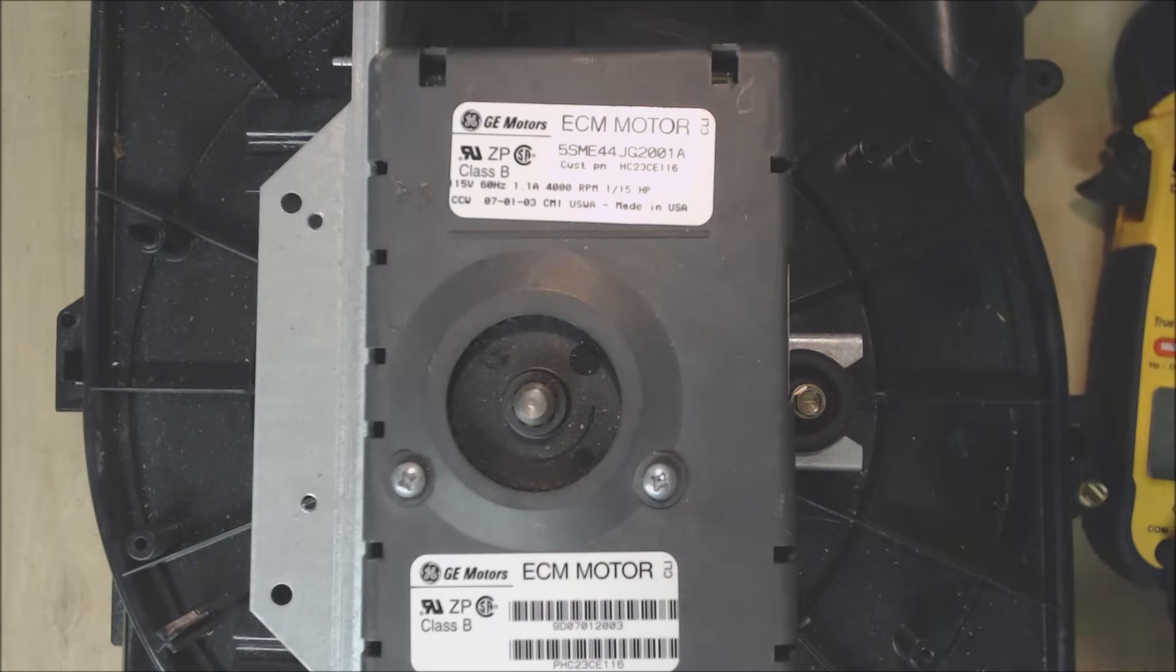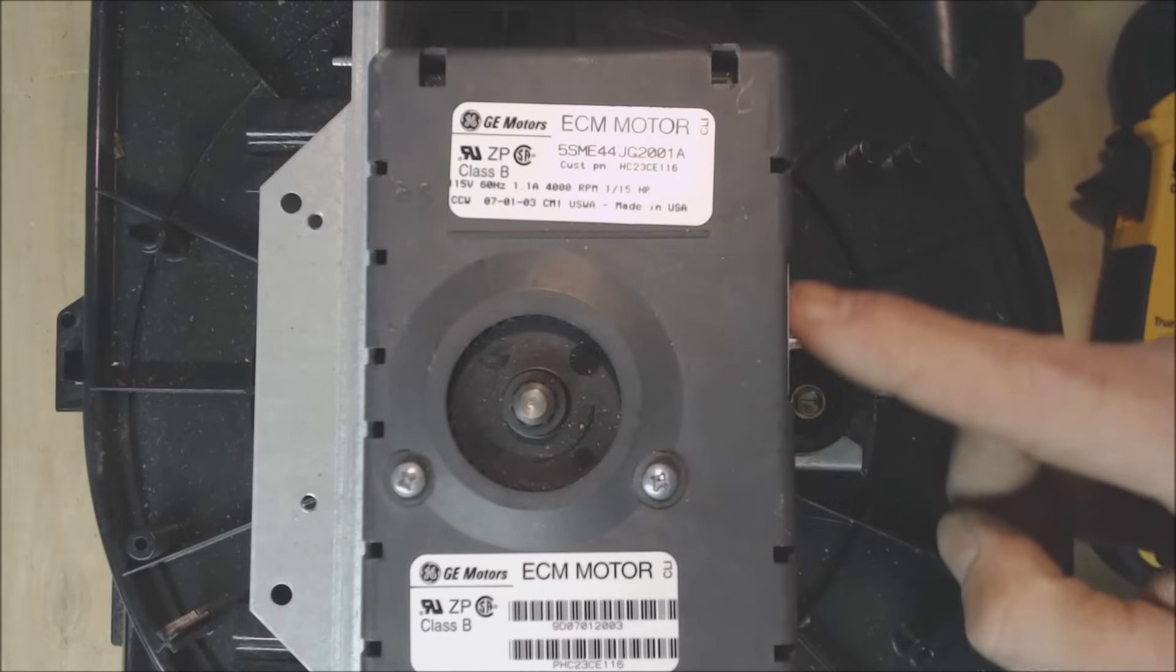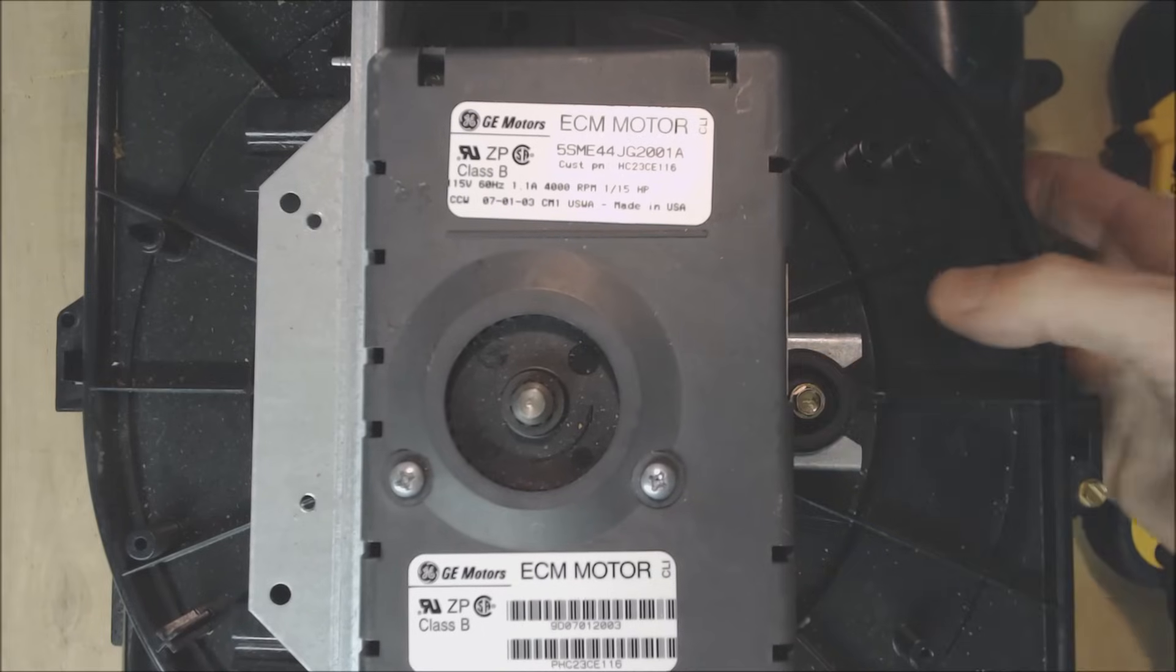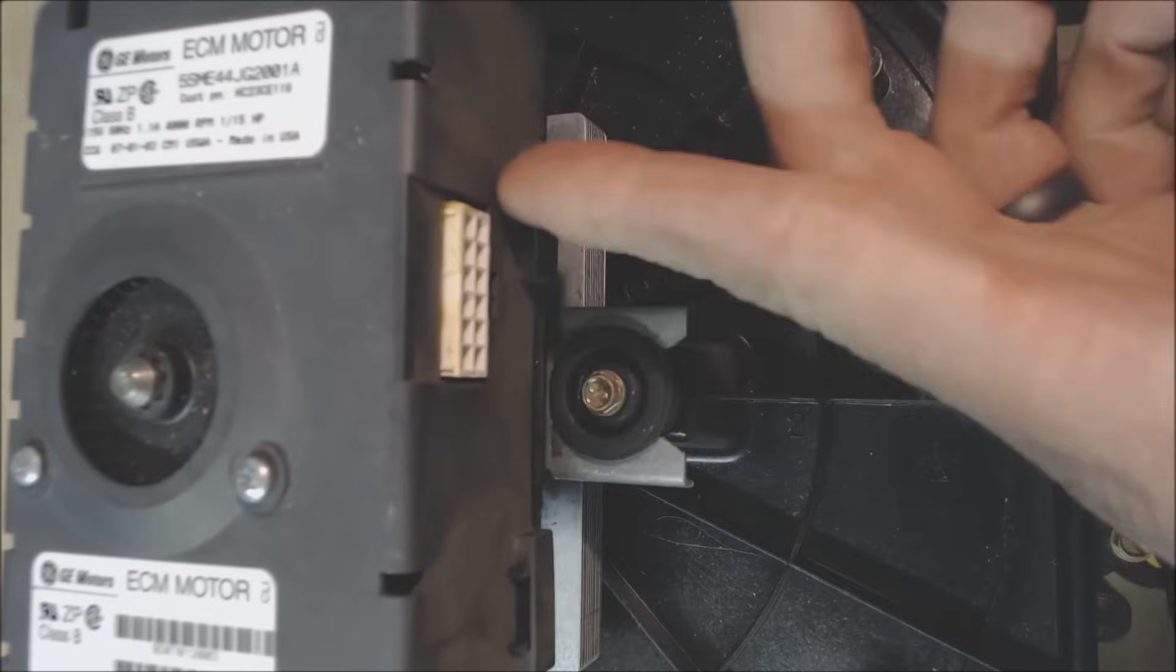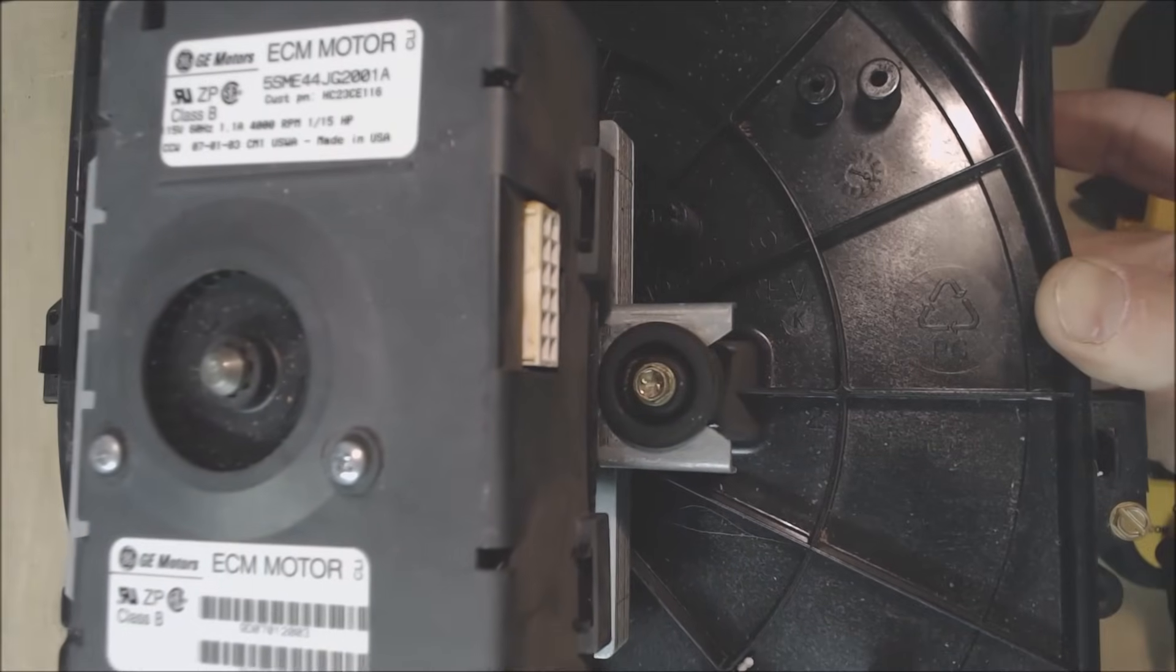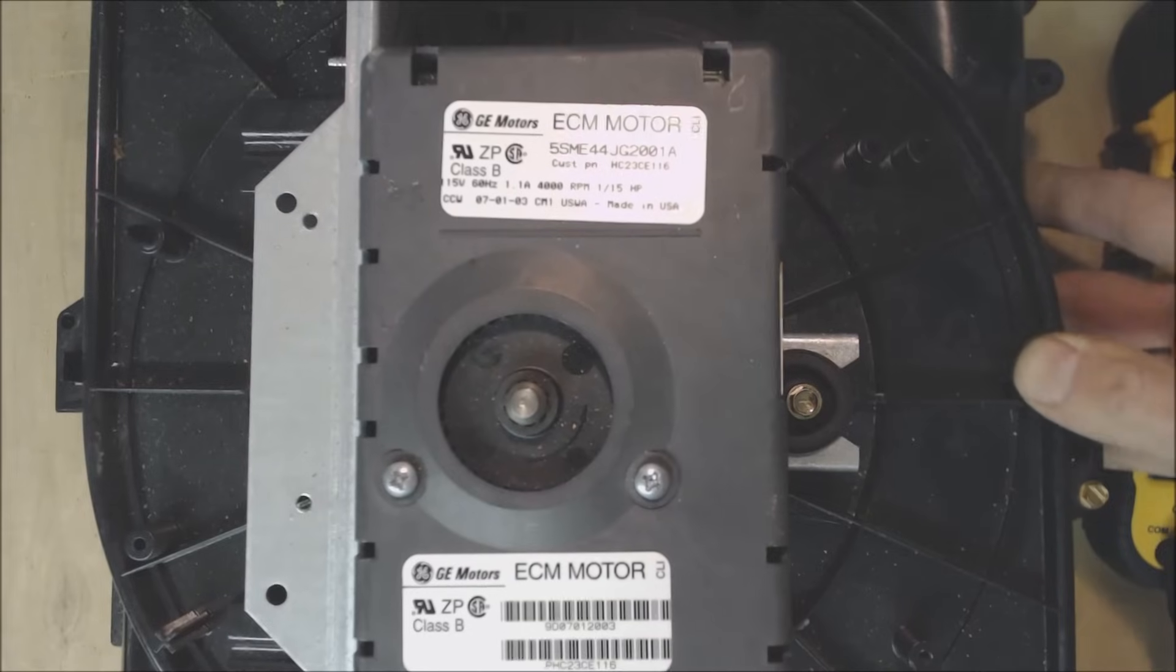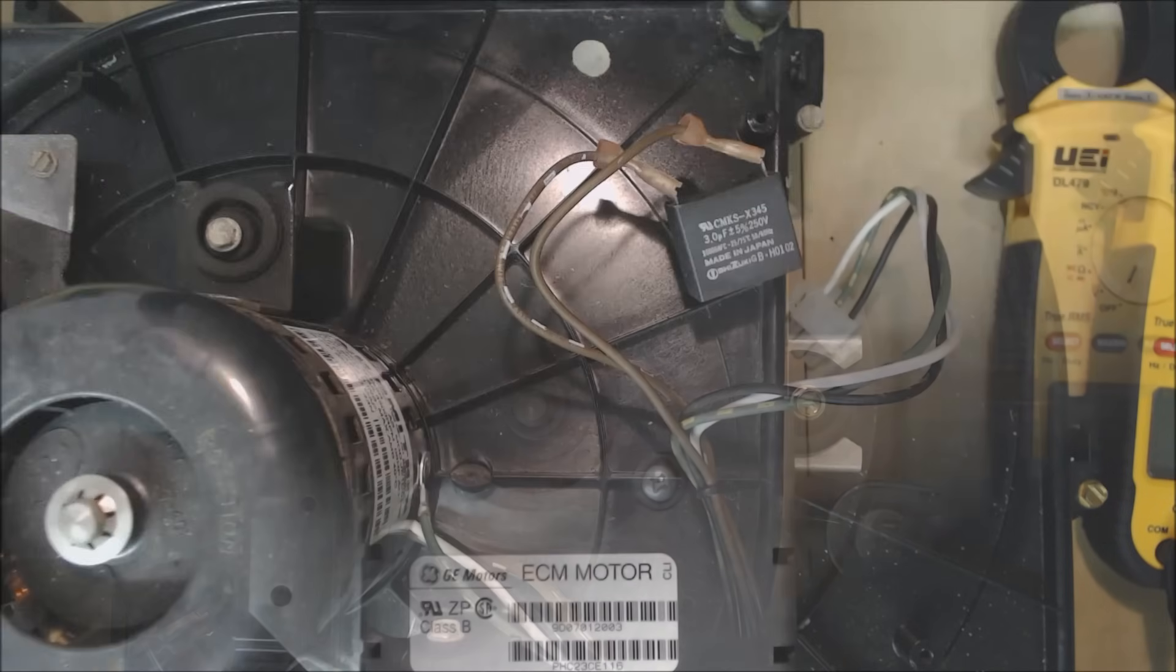In reference to checking ECM variable speed inducer motors what you need to do is actually access the troubleshooting guide for that model number furnace and typically on the side right here there's going to be a connector that you're going to have to check DC voltage readings off of. You're going to follow what the troubleshooting guide says from that manufacturer and you're going to see the DC voltage values changing.